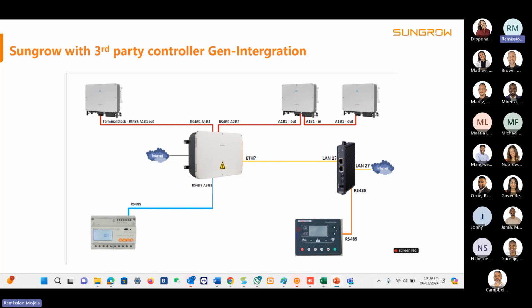Then if your controller communicates via RS485, you can still take this controller and put it on the third port of the Logger 1000. Or if it communicates via TCP, you can just plug it on a switch, together with the Logger 1000 plugged to that same switch, for them to be able to communicate. So this is the basic setup. If your controller uses RS485, then you just plug it directly on the inverter. If it uses TCP, you can plug them to a switch.